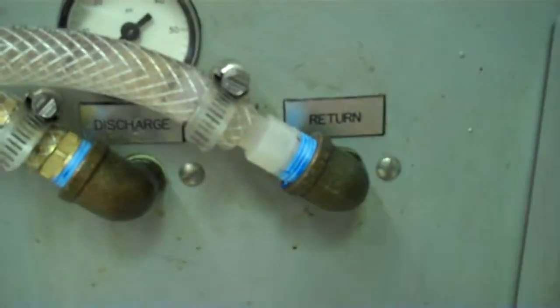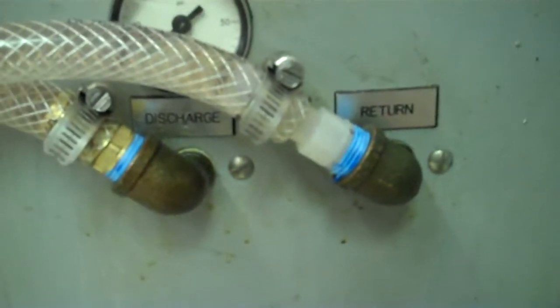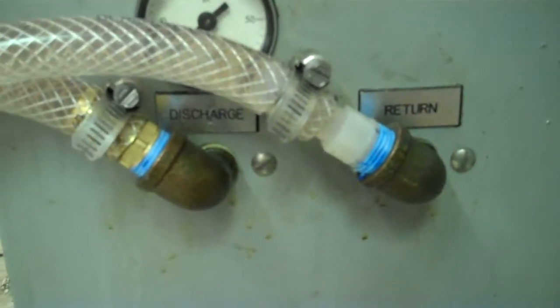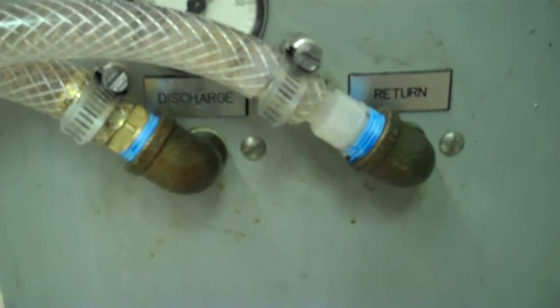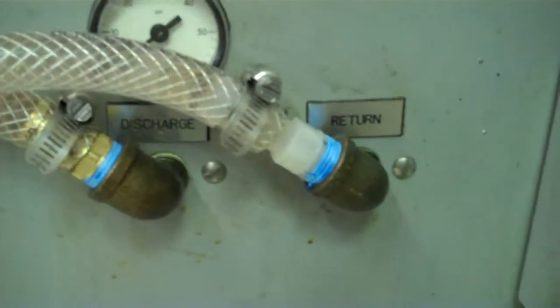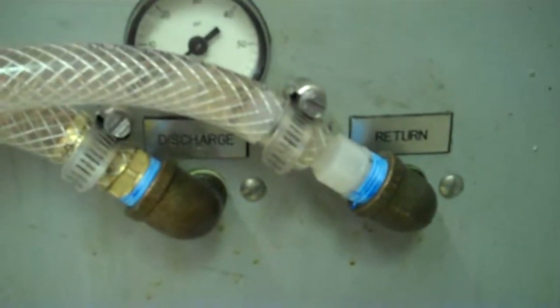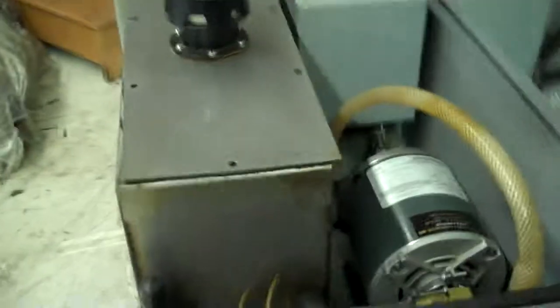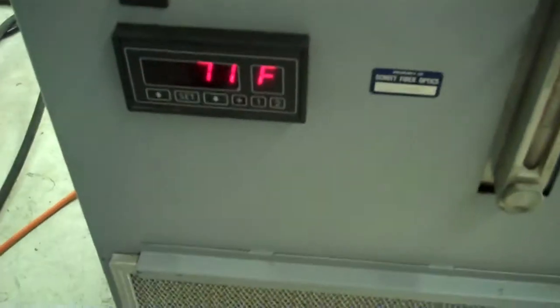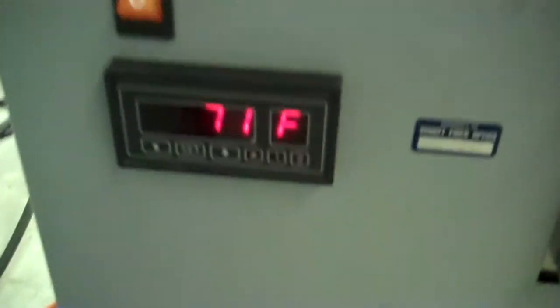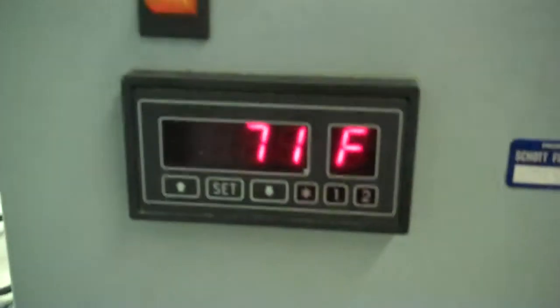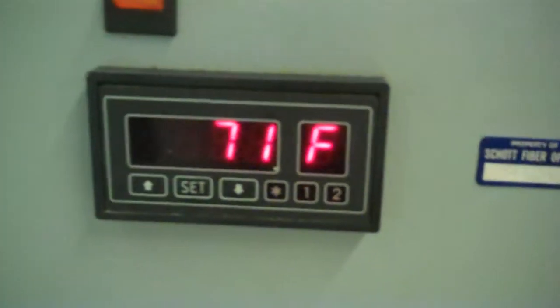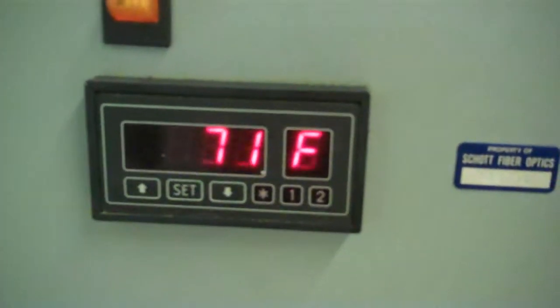Otherwise, it's going to be strangling the system, and your pump's going to go into overload. That's very important from a process piping standpoint. It's also very simple to do. And when you're doing bypass, you should have a shutoff in there. You can see now, we're chilled down to 71.